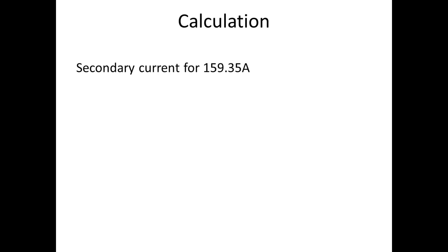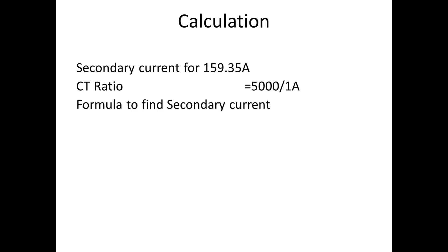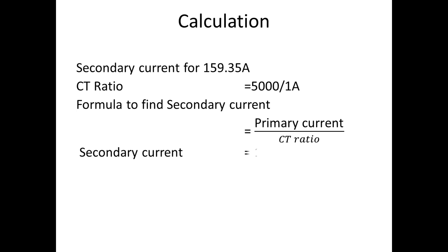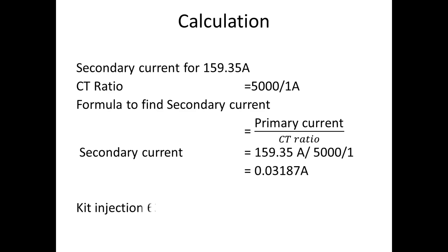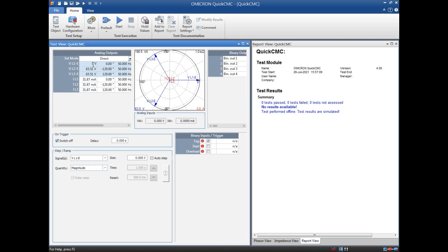The value which I got is primary current. But for testing of this function we need to inject secondary value, so now I am going to find the secondary current. The CT ratio is 5000 / 1. The formula to find the secondary current is primary current divided by CT ratio. The secondary current is 159.35 amps divided by 5000, which gives 0.03187 amps. For the kit, we have to inject 63.5 volt and 0.03187 amps — that is 31.87 milliamps — into the relay, and we have to wait until the trip time which we have set in the relay.